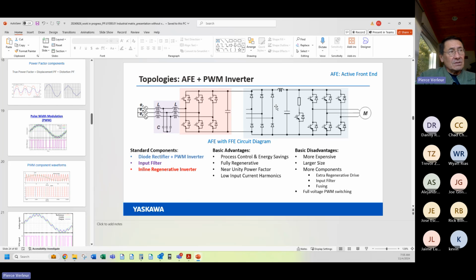And you can prove that by just noting the capacity of these capacitors. Again, this is a 100 horsepower motor, it's 75,000 watts, right? It's 750 watts to the horsepower. So at 75,000 watts, these capacitors get drained out in a millisecond. Not much backup. That's one fact. The other fact is this.